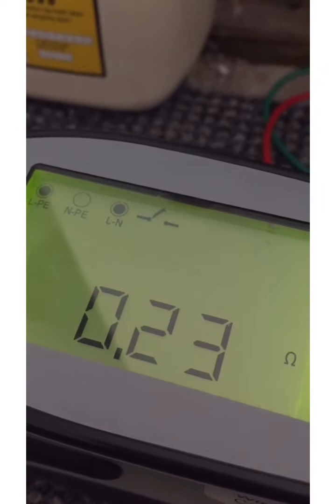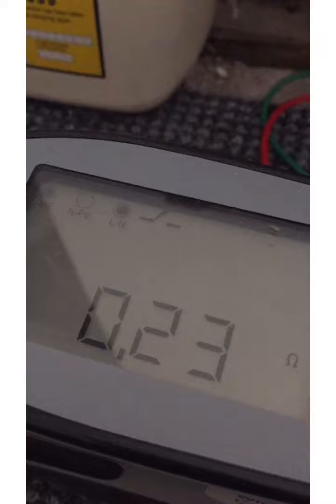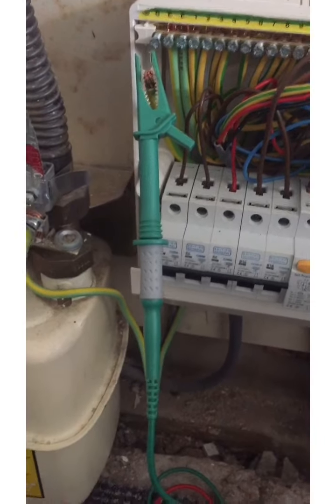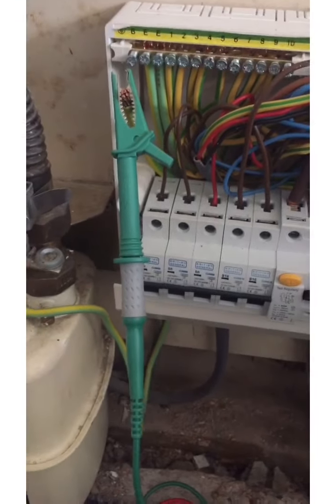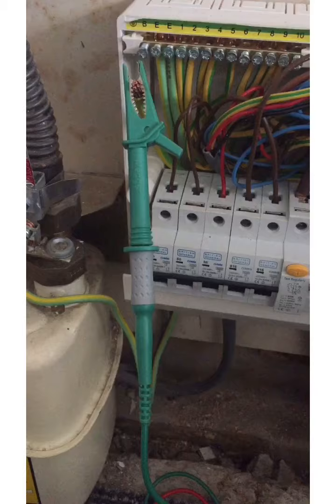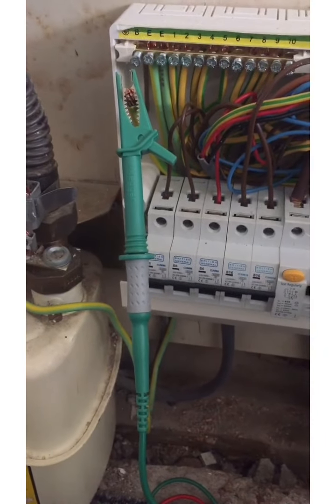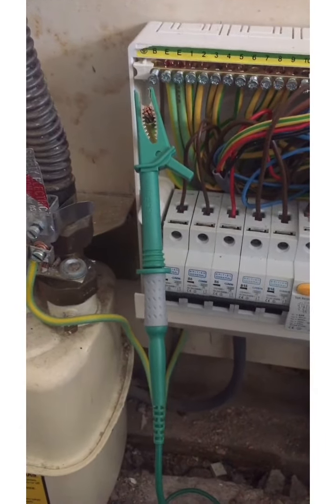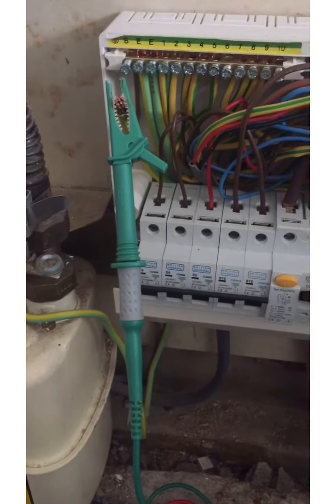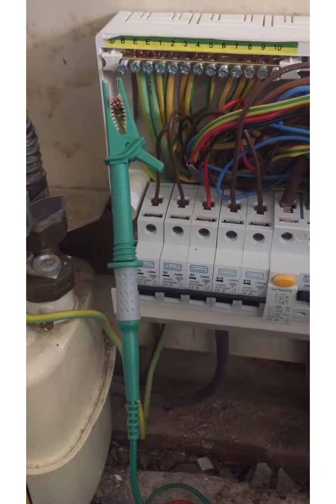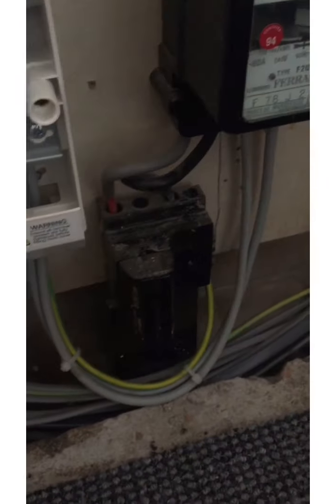0.23. So back to that again. I would take out of those, obviously, the worst case scenario, which is 0.25. Now, once we've taken that value, what are we going to do with it? Well, the reason why, very importantly, why the earthing conductor is disconnected is to remove any parallel paths, to make sure that we're just testing the ZE and nothing else. We're not testing earthing through pipework or other means. It's just that incoming earthing conductor connected to the means of earthing.